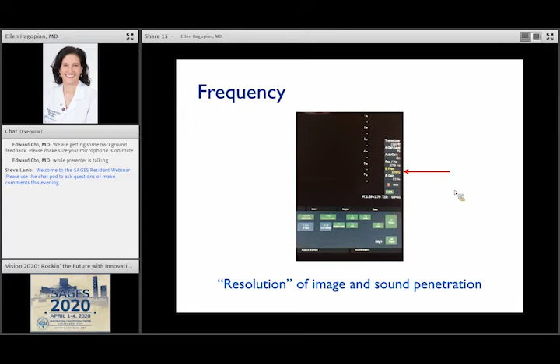So this is an example of the same exact image, but with two different frequencies. The image here on your left is at 5 megahertz, as opposed to on your right is 13 megahertz. So what I want you to do is look at right here. You've got some sort of a structure right here. And at 5 megahertz, which doesn't have great resolution but has better penetration, we think, well, is there something there? Well, then we change the frequency, and then we see right here, there's actually a vessel there at 13 megahertz.